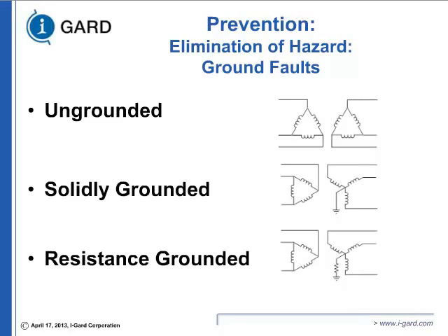One method is to look at the system grounding. You have three kinds of grounding system that you can categorize. Ungrounded system, where your secondary side, where you're using it, does not have an intentional ground. People who are true electrical engineers will challenge me: there is nothing in the universe that is ungrounded. That is true. Ungrounded here means not intentionally grounded. Every system is capacitively coupled to electrical lines. Next is solid grounded, which is the most common use. The ideal system to use is resistance grounded, and we'll explain how it benefits.